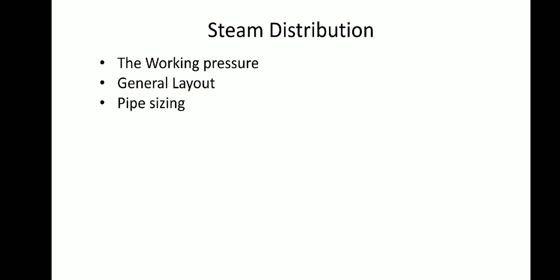Then pipe sizing. The objective of a steam distribution system is to supply steam at the correct pressure to the point of use. It follows therefore that the pressure drop through the distribution system is an important feature. Proper sizing of steam pipeline helps in minimizing pressure drop. The velocities for various types of steam are: superheated 50 to 70 meter per second, saturated 30 to 40 meter per second, and wet or exhaust 20 to 30 meter per second.